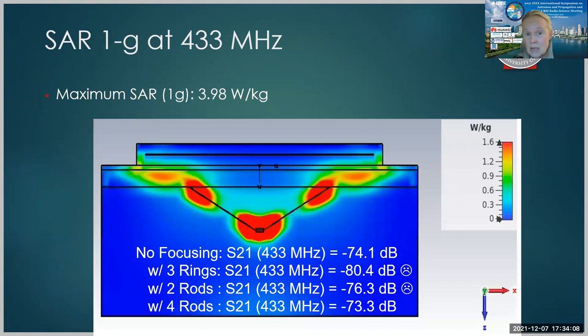Well, again, we can see substantial increase in the SAR. In fact, we've increased the SAR almost double at this point. But again, not a lot is being picked up by the internal IMD antenna. So we do need to do a better job with the IMD antenna design if we want to be able to use a coil system.